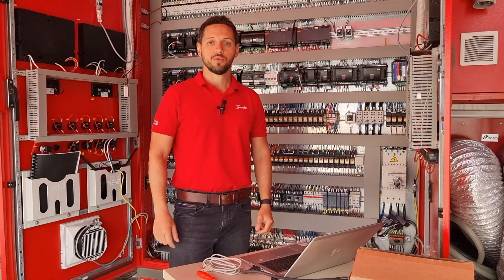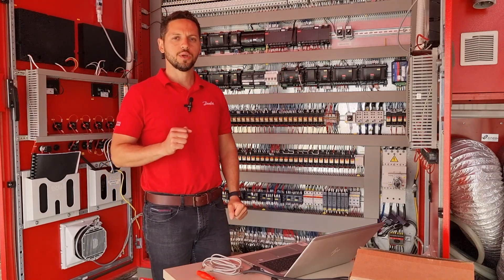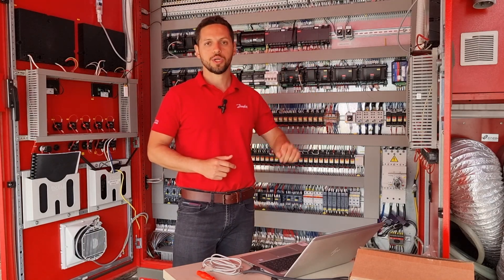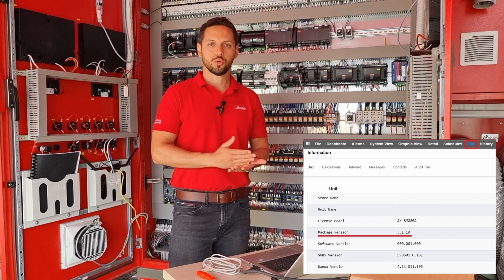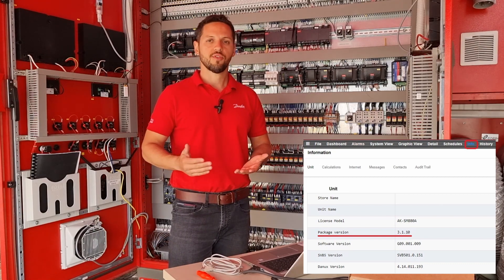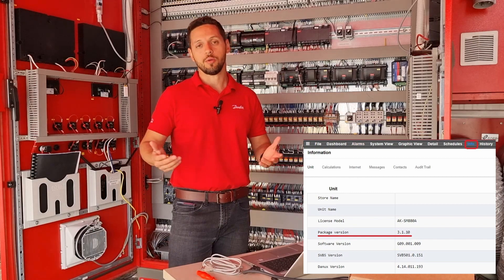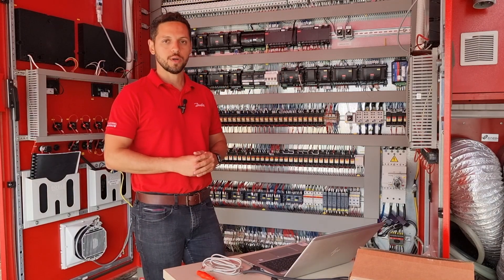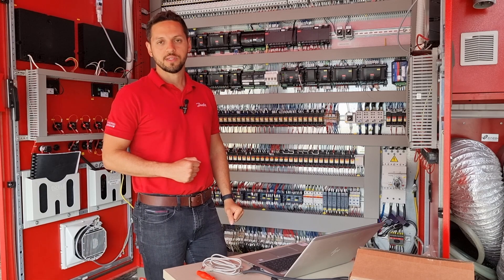Now let's get started with the replacement of our AKPC-782A. But before we start, I would like to give you a very important advice. Always check the version of your system manager AK-SM880A. It's very important to ensure that you are running software version 3.1.10 or the latest version. The 3.1.10 is the first version which we released that accepts communication with the AKPC-782B. Now that we have ensured we have this version in our system manager, let's get started.